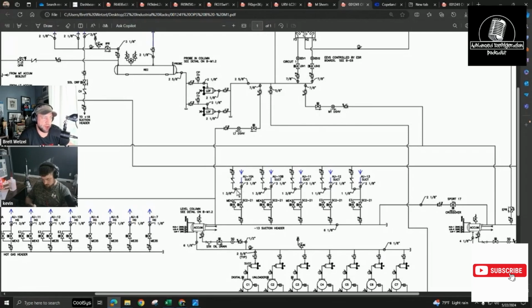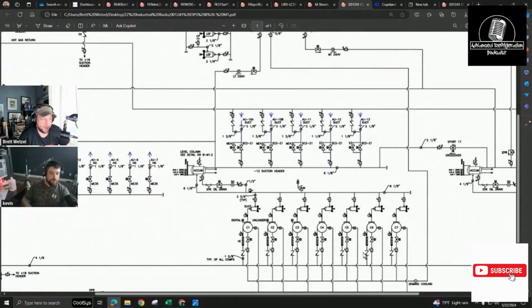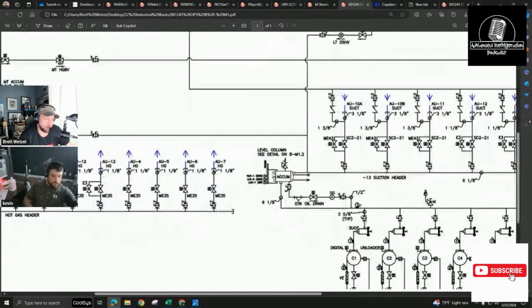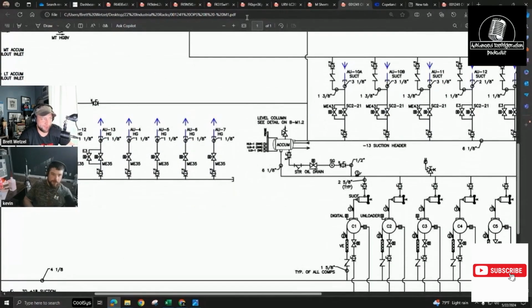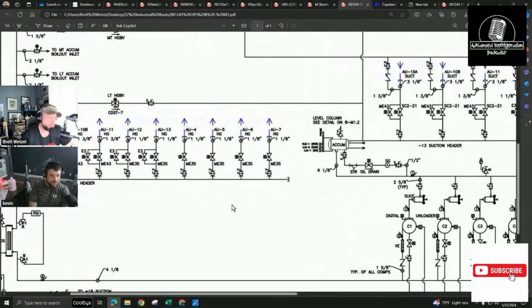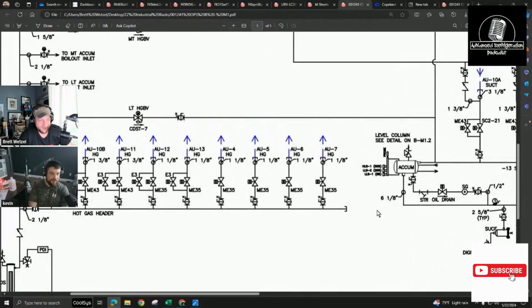that you're getting back. So they are preventing it a little bit with the pump out solenoids here, but on top of it you have this huge accumulator connected to it, which is basically acting like a buffer so we don't grenade our compressors. If you look at the pipe size, that has to be a huge accumulator. Oh yeah, that's a big accumulator. Like that's 6 1/8. Is this 6 1/8? Yes, it is. Suction header.